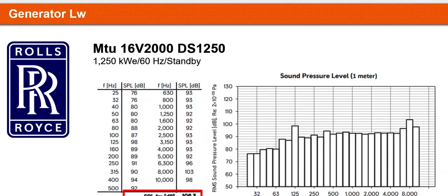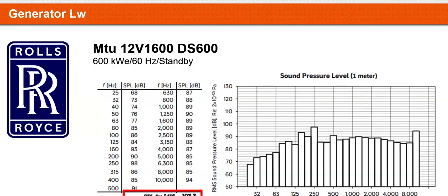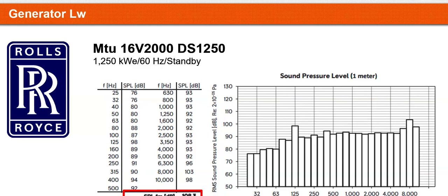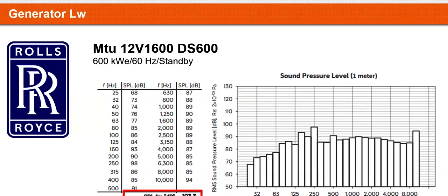So I'm hoping that once they install this and I go and measure, I have finally a project that's at the design stage and not after the fact. But in this case, they do have two standby generators. One is bigger, one is smaller. The smaller one is 600 kilowatts. But even though these are not as big as they get, you could tell that at 1 meter out of the louver, they are at 107 decibels. So still, you could damage the ear permanently within a couple minutes at these levels.